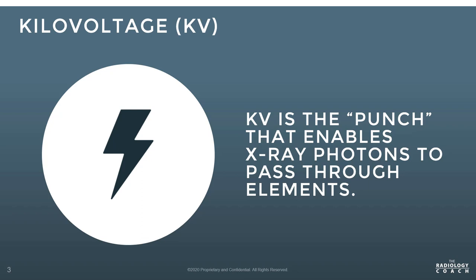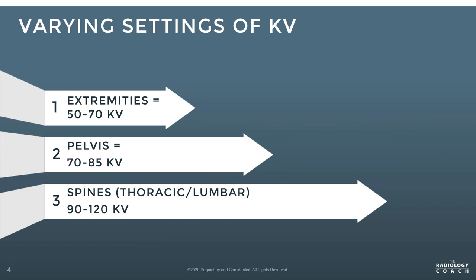KV is the punch that enables x-ray photons to pass through body elements. You need enough strength in your settings to penetrate a body part. Typically in the podiatry world, we look between 50 and 70 KV to adequately penetrate through the smaller foot and ankle elements. Your standard settings for extremities would be in that 50 to 70 KV range.